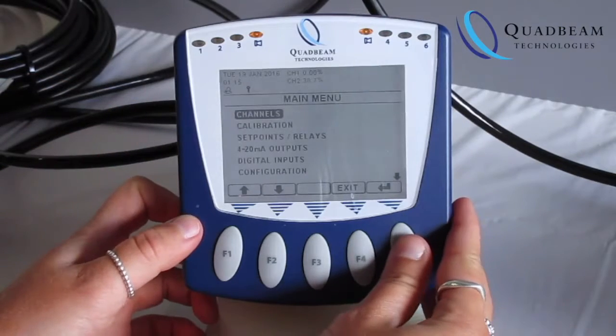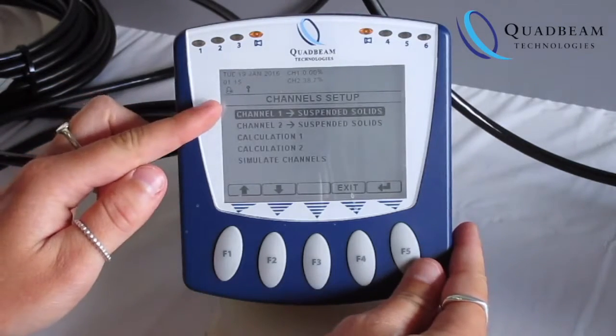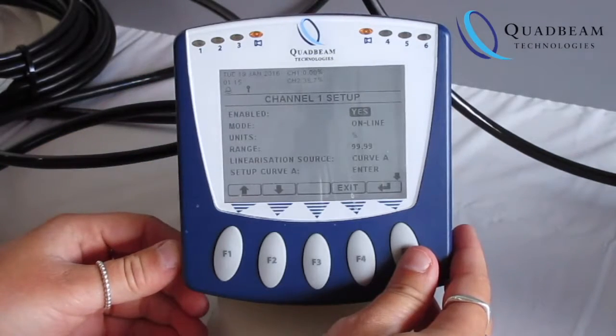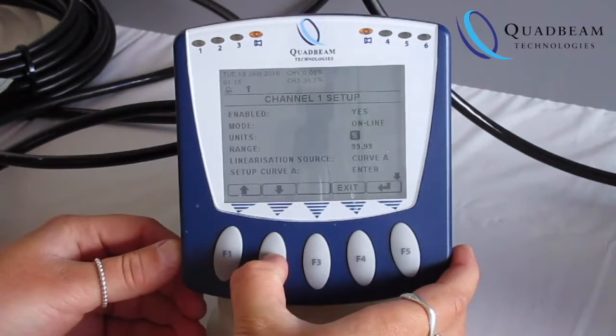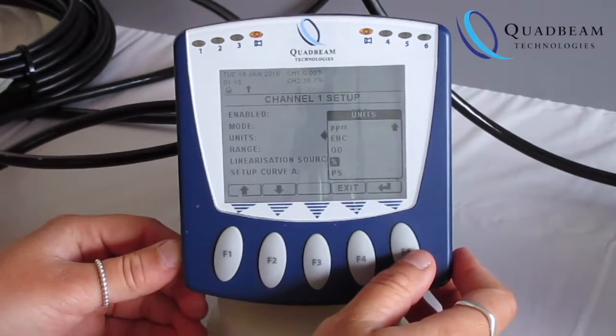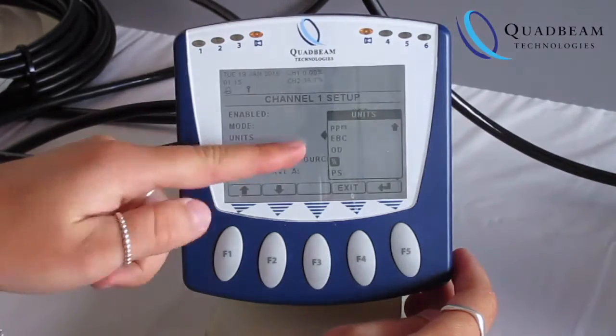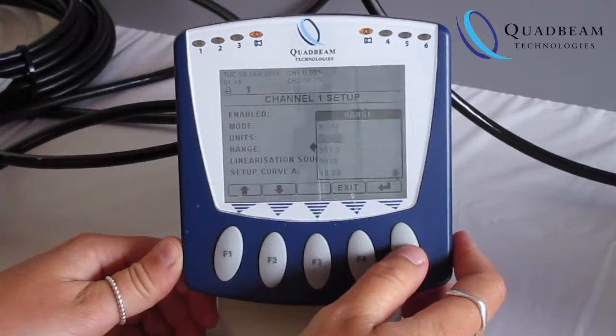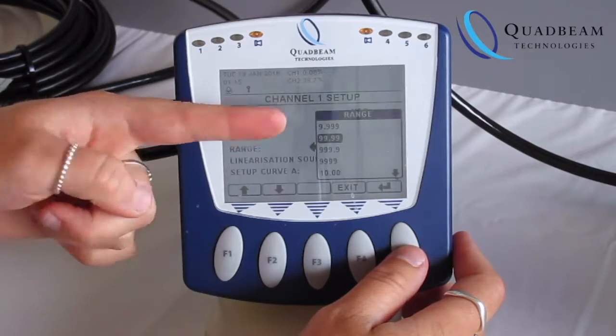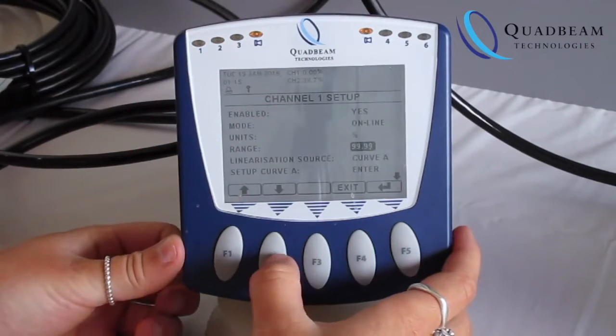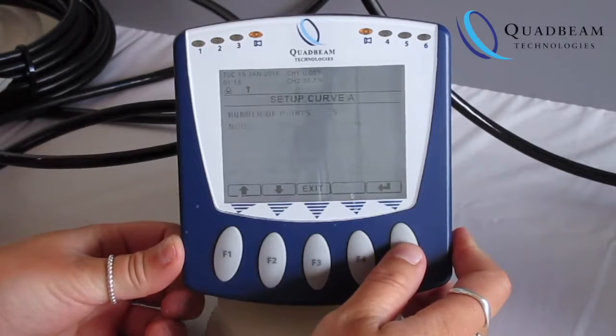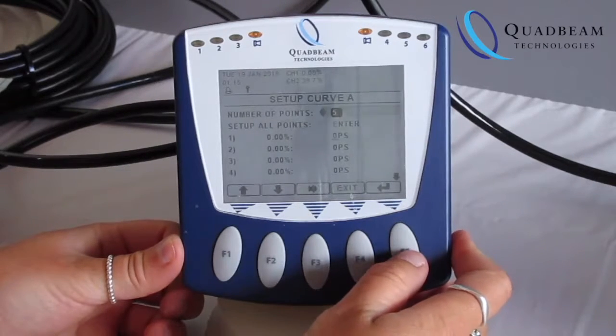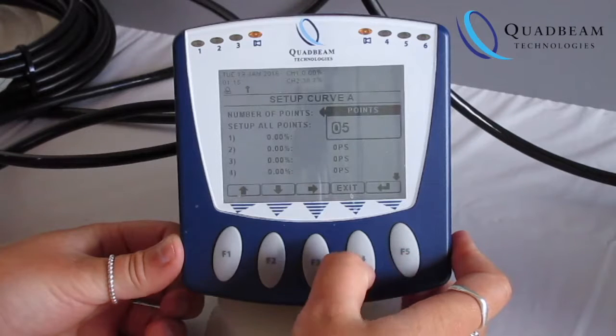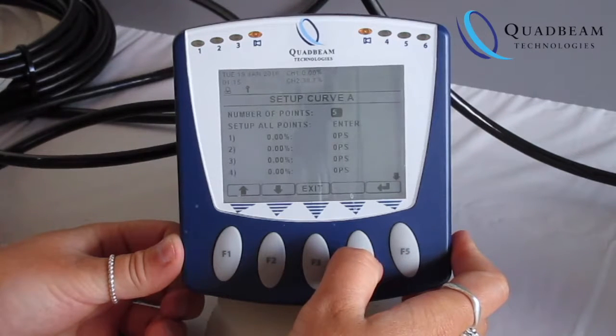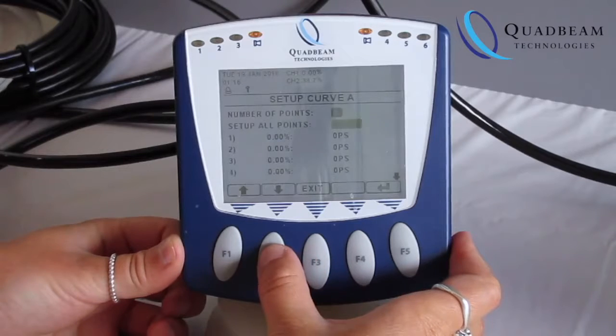So to do that, we move to channels, pick the channel, in this case channel 1, move to units and ensure that that's percentage, as that's the value that we're wanting to use as a measurement value. The range in this case needs to be 99.99, as we want 2 decimal points. Move to setup curve A. We've got 5 points. Any less would not be acceptable for this type of application. 5 will give good accuracy.